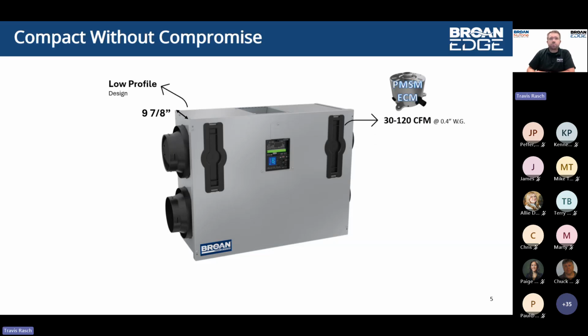Just like our other products, meaning our AI series products, our Broan 1, this new Edge product will utilize the same PMSM ECM motors. What that does is not only provide energy efficient operation, but also the ability for the product to be dialed in 1 CFM increments. So in the case here, you can go from 30 CFM all the way up to 120 CFM in those 1 CFM increments, allowing you to adjust this product, again, depending on the application. If you have a multitude of different floor plans, like in a multifamily application, where floor plan A is this certain square footage, or this number of bedrooms, and floor plan B is different, you still have the ability to specify that same SKU and dial those CFM requirements in. You're not stuck with maybe a low and a high, or low, medium, high speed settings. You can dial that in as you see fit, utilizing that integrated LCD screen you see in the middle of the product.